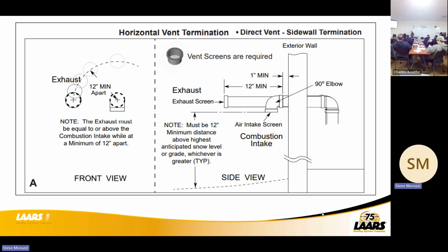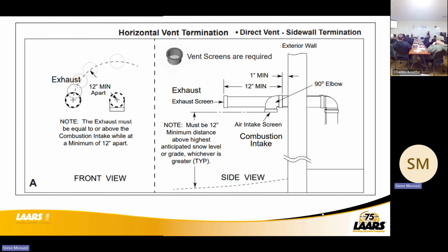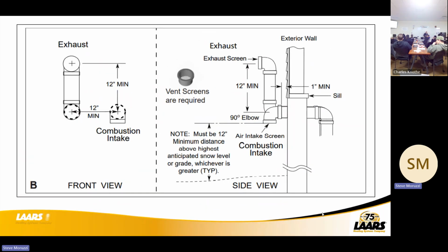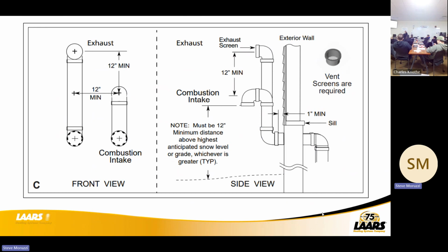All right, and we've talked about this before. Again, you should not be flush mounted with your exhaust and combustion air flush to the building. Your exhaust should be extending beyond, especially in low fire. You want to get those flue gases out and away with less opportunity of flue gas recirculation. A better option would be come out of the dwelling, 90 up, and get a minimum of 12-inch separations there. All right. And same if you're concerned about snow level, get that up as well for the combustion air and exhaust.